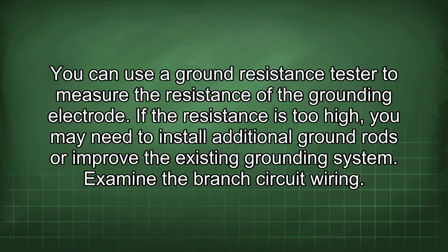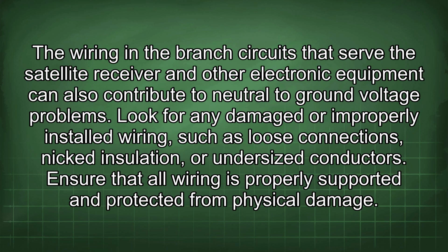Examine the branch circuit wiring. The wiring in the branch circuits that serve the satellite receiver and other electronic equipment can also contribute to neutral to ground voltage problems. Look for any damaged or improperly installed wiring, such as loose connections, nicked insulation, or undersized conductors. Ensure that all wiring is properly supported and protected from physical damage.